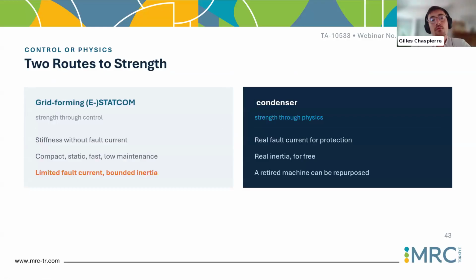Yes, so there has already been a quite extensive and nice overview of all the technology that exists to control the voltage, I would say. Here it's really what can TSOs do to increase their stability margin, in other words, increase their system strength. Well, there are mainly two assets. We discussed already the STATCOM, but I will insist here on grid forming STATCOM, because classical STATCOMs are still relying on grid following control, meaning, okay, a STATCOM can provide reactive power reserve, fast voltage control, but it's effective as long as the grid is strong enough.